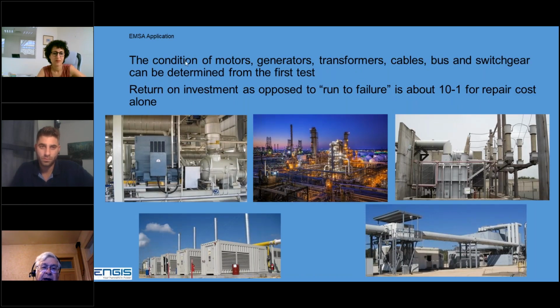The condition of motors, generators, and transformers, bus, switchgear, can be determined from the first test. Trending is important, but not necessary to identify a problem. The return on investment to pay for doing the test versus run to failure on equipment is about 10 to 1 just for repair costs, not lost production. Here's testing a large compressor motor at a site, emergency standby generators, a refinery. We also test transformers, the bus, and on the high voltage side of the transformers out into the switch yard, we can find problems. And then the more common large generators, the isophase bus, and the breakers on the bus.